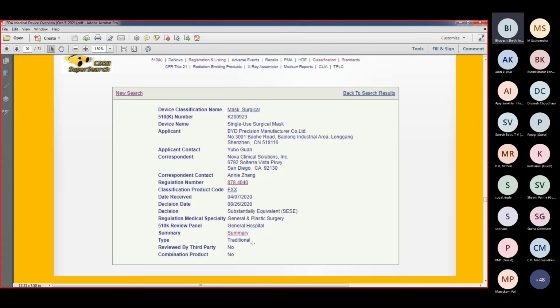Most importantly, you can find a 510K summary. Now, sometimes you'll only find a statement here. A statement doesn't give you much except the intended use, but a 510K summary gives you more details. So a lot of times we are asked the question by our clients, how can they find more information about a predicate device? Or how can they find official information about the predicate device rather than relying on just the predicate's manufacturer's website? So this is one option.